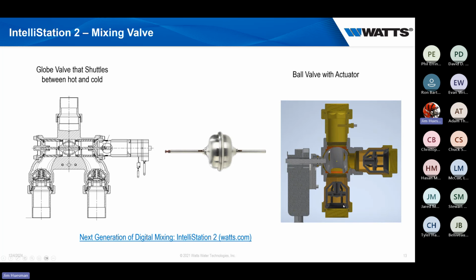This check valve is actually the same check valve you'll find in our Watts 007. It's a well-built, tested check valve that really ensures when our hot's starting to cross over, we'll have a complete shutdown. If you've ever worked on a building cross, you've had hot water in the toilets and cold water coming out of the bathtub on both sides. It's an absolute nightmare, and you'll spend hours trying to find out, hey, I have one bad check valve on my mixing valve.